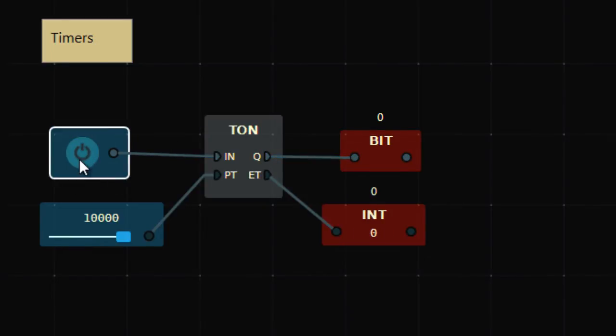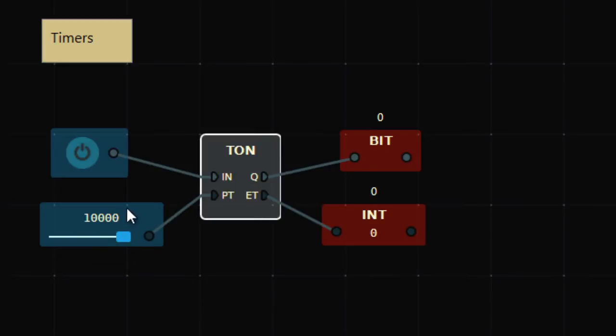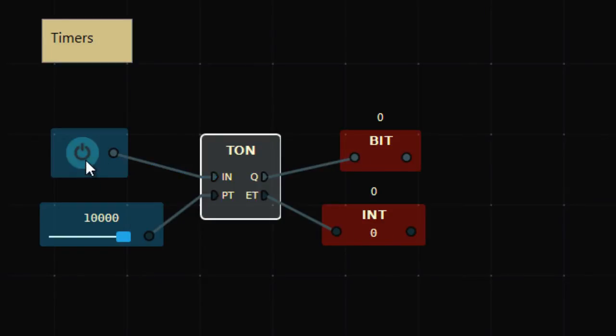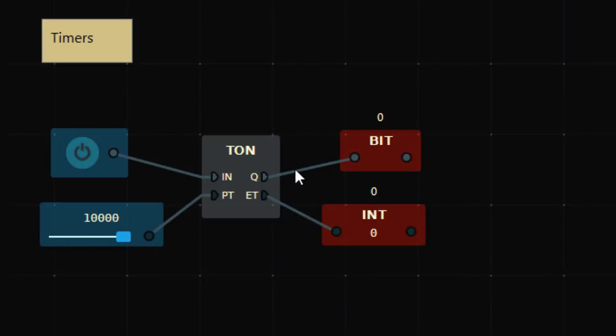One thing to notice: I have to keep pressing the switch. If I release it in between, the timer resets. But I may have an application where I just want to press it once, then after 10 seconds the output should be ON — I don't want to hold it for 10 seconds.